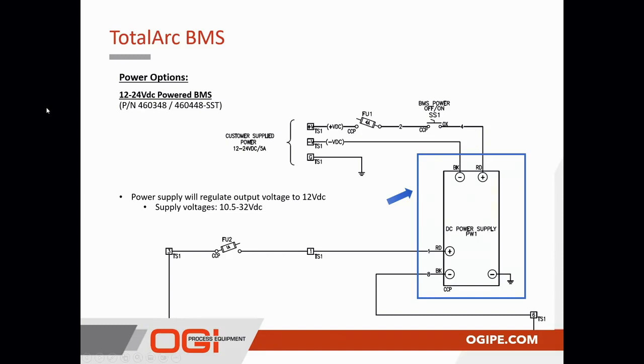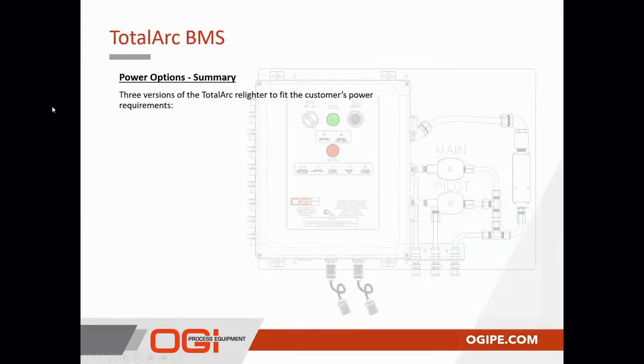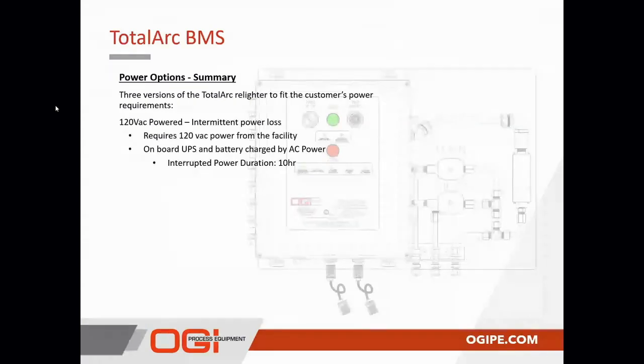Just in summary, these three versions of the TotalArc Relighter are set up to suit most customers' power requirements. Again, the 120 volt system does require 120 volts AC powered from the customer's facility. As I stated, it's intended to be more of an intermittent power loss system. It's not a long-term power loss system. It does have an onboard UPS system and a battery charger for its UPS augmented battery supply that allows that BMS to operate for 10 hours in the event that we lose primary power.